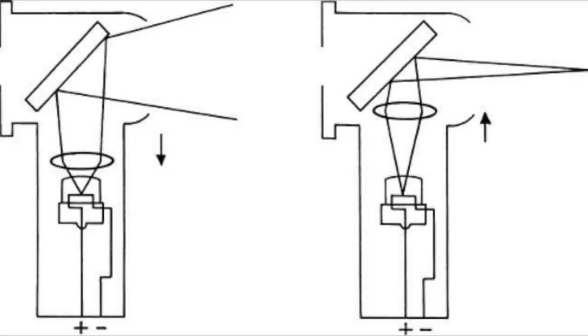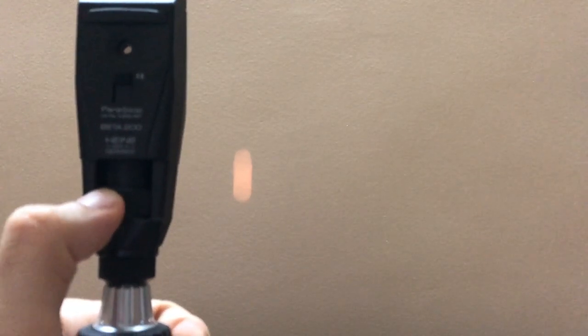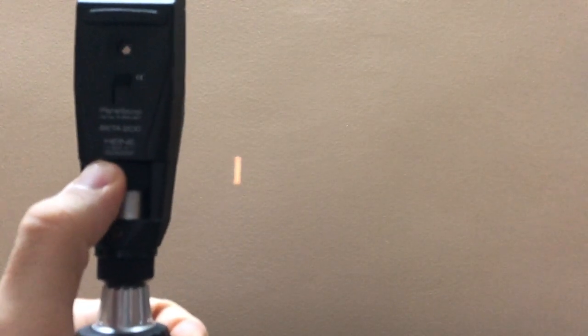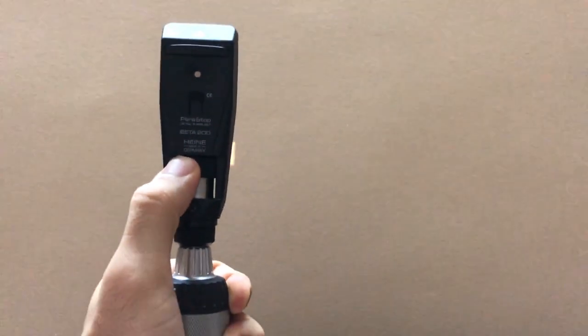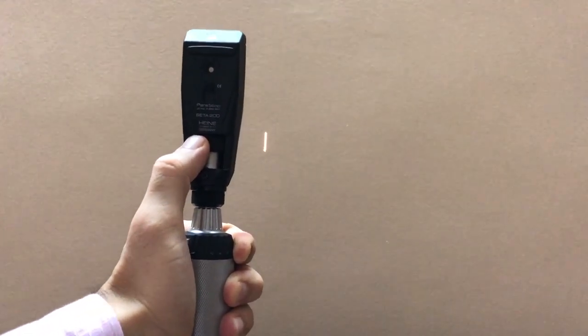With the touch of a finger or thumb, the practitioner can alter the streak so that it leaves the retinoscope as converging, diverging, or even parallel light. This feature gives the practitioner an incredible amount of power in evaluating a patient's refractive state. The lowest position gives a divergent beam; the highest position converges the streak at a distance of 25 centimeters in front of the retinoscope.